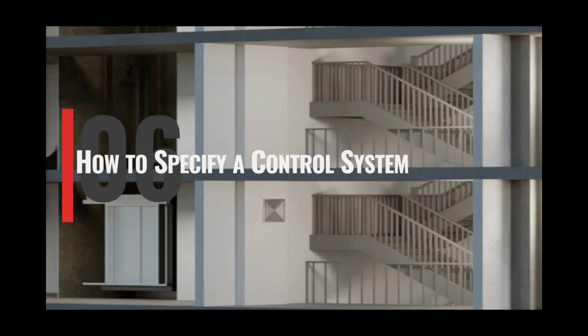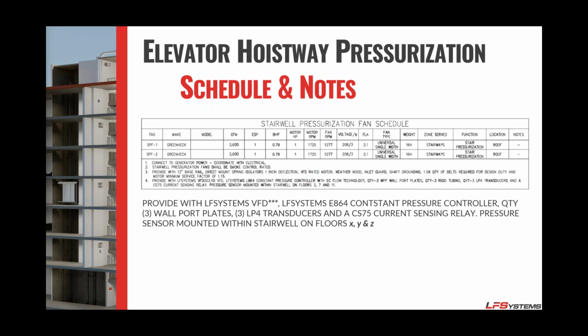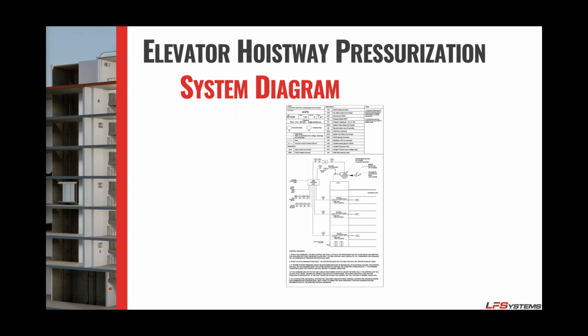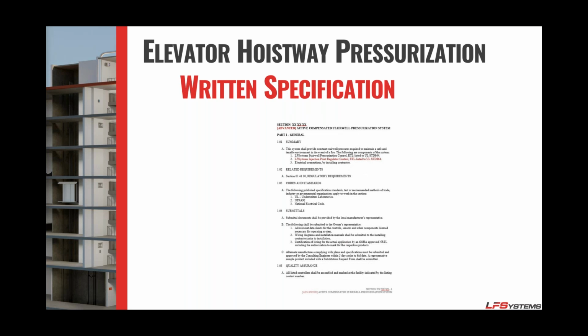So how do you specify this? The one question I always get is, who covers this control? We like to have it tied to the fan. When you're specifying your fan, just put it in the notes to provide it with LF Systems, VFD, controller, et cetera. We also like to reference the system diagram, which we can provide you in both PDF and CAD. It'll have a sequence, the diagram, and all the notes that are required. We can also provide a written specification for the control systems that you can tie into the rest of your smoke control system.